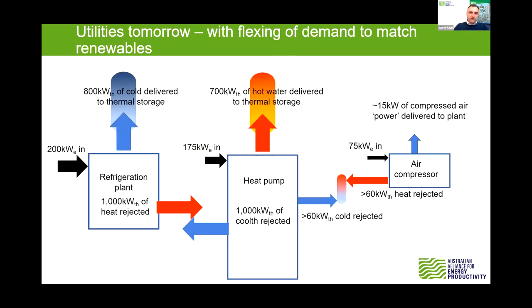One other alternative is to combine that with thermal storage on the demand side, or flexing your process up and down. Rather than storing hot water in between the refrigeration plant and heat pump, you may choose to run that during the middle of the day when there's plenty of cheap solar power, and just store up the heat that you may need for the process throughout, say, a 24-hour period.